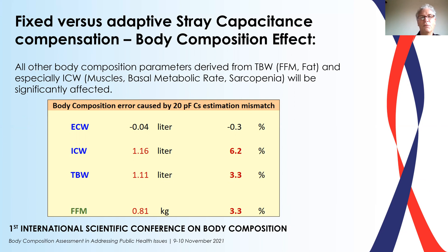You can see from this table that a compensation error of just 20 picofarads — and a typical subject could vary anywhere between 10 and 60 picofarads — means that with a 22 picofarad fixed compensation, it's not difficult to see that you'd have quite large errors. The intracellular water has a 6.2% error just from having a mismatch. Yet as an end user, you wouldn't realize it, you wouldn't know that existed. Total body water shows a 3.3% error, and fat-free mass a 3.3% error.